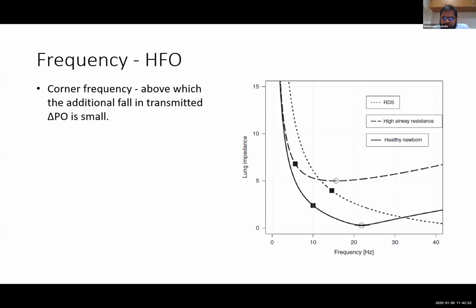Usually that depends on the baby, but in a healthy newborn you will see that the corner frequency is around 10. Around a frequency of 10, above which the fall in lung impedance will be minimal. So you will start with a frequency of 10. You will not touch this parameter routinely whenever you are adjusting your ventilatory settings. If the baby is having ventilation issues and CO2 is high, you will touch the amplitude, not the frequency first, because this is the corner frequency which we are using for these babies.